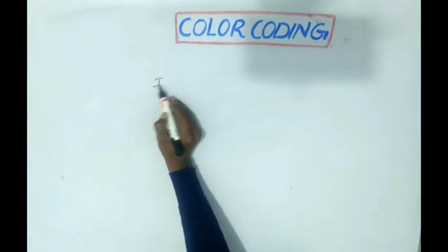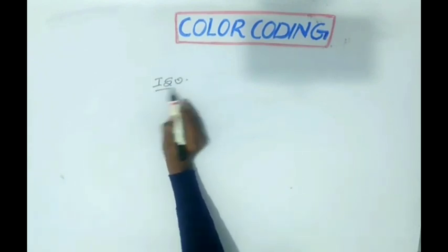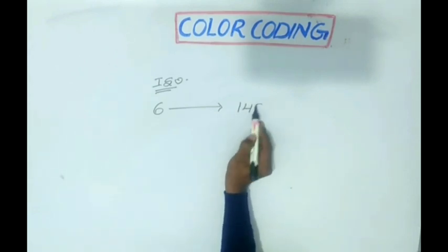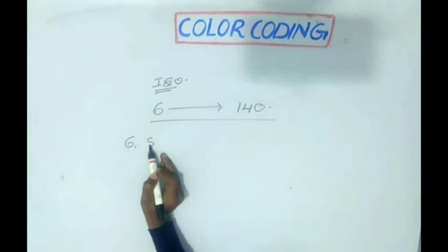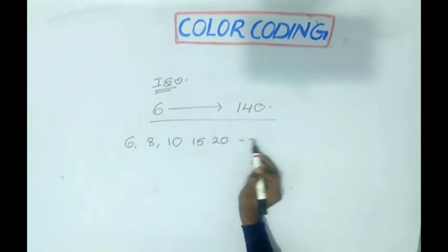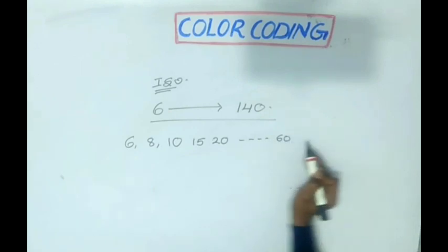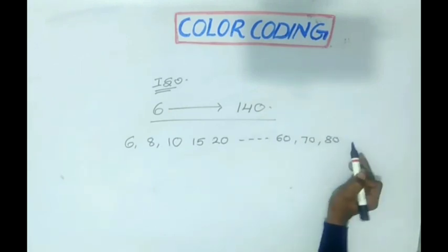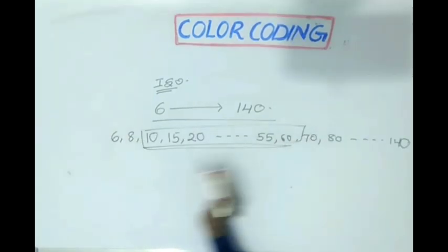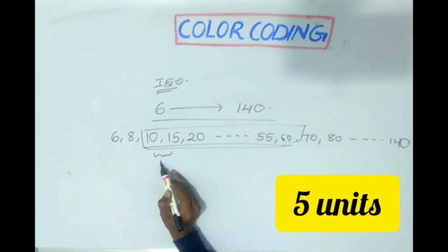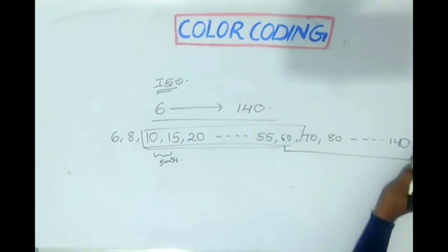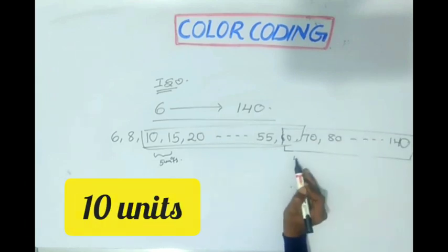According to the ISO standardization, endodontic instruments are ranging from 6 to 140 — that means 6, 8, 10, 15, 20, and so on to 60, 70, 80, and so on to 140. If you observe, from 10 to 60, the number advances by 5 units, whereas from 60 to 140, the number advances by 10 units.